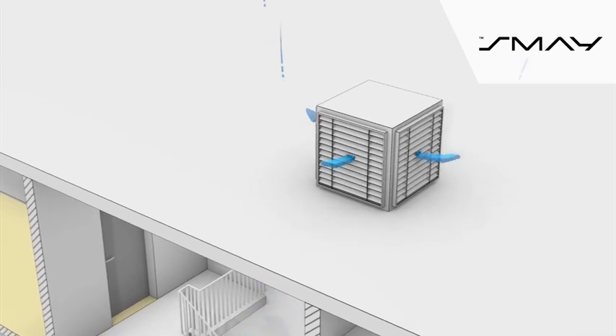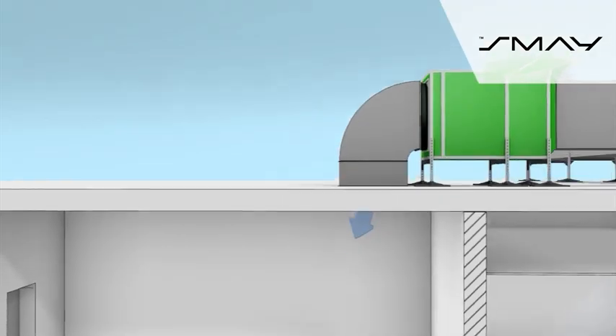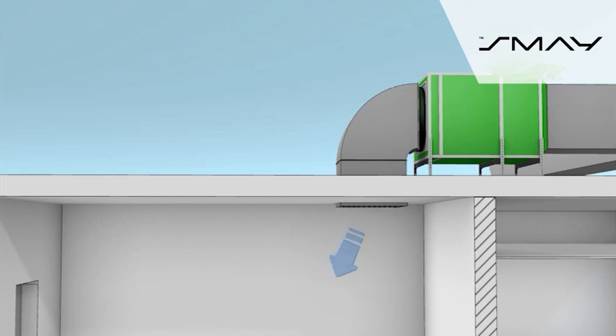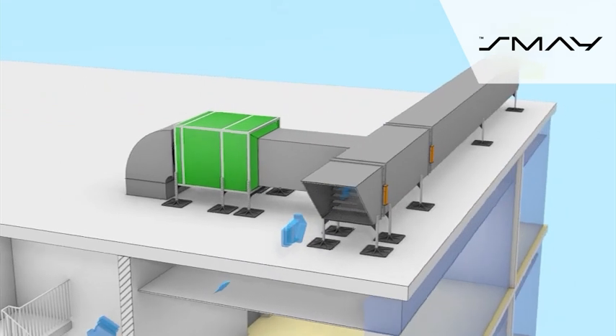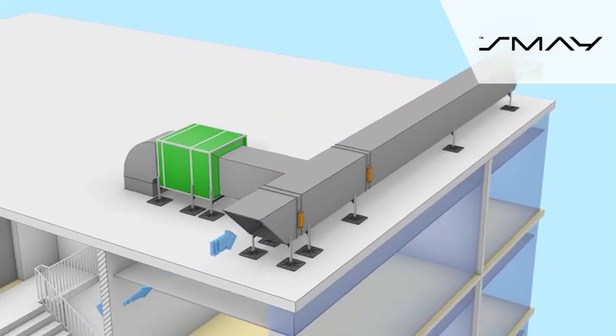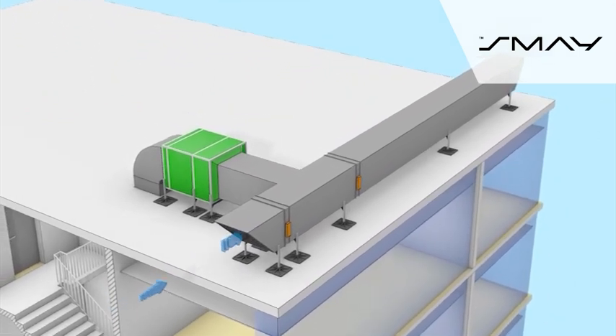If the iSWAY-FC units are located at the roof, which usually results in concentrated air supply through the ceiling of the staircase, it is recommended to provide a twin air intake system with, if possible, air intakes located at opposite building facades.